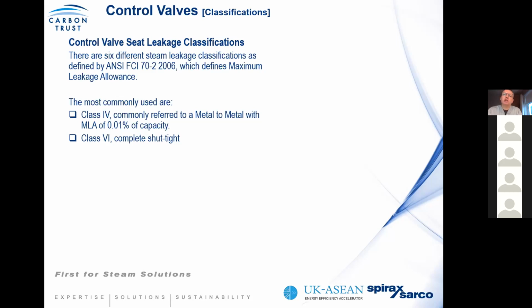From our own lab analysis, where we have taken different types of valves and stressed them to normal operating conditions, what we have found is that although it might be a class 4 on installation, within a very short period of time, 6 months to a year, you're at a class 3. So in other words, you have high leakage rates. It's therefore far more economical to look at the class 6, which is designed to give complete shutoff. Because you need to consider the different types of valves.